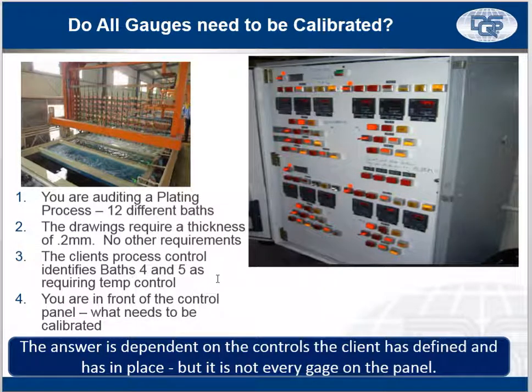So this is the toughest scenario for us to deal with. And really, it's down to what is required of that process, and how the customer is defining process control. So in this case, it's only a thickness. I didn't say anything about adhesion or any of the other properties that might be considered in a plating process. And the customer has identified that they do want baths 4 and 5, which probably have to do with concentrations, to be temperature controlled. So in that case, all these gauges that you see on here don't necessarily need to be calibrated. Only a couple of them, the ones controlling baths 4 and 5, would need to be calibrated.